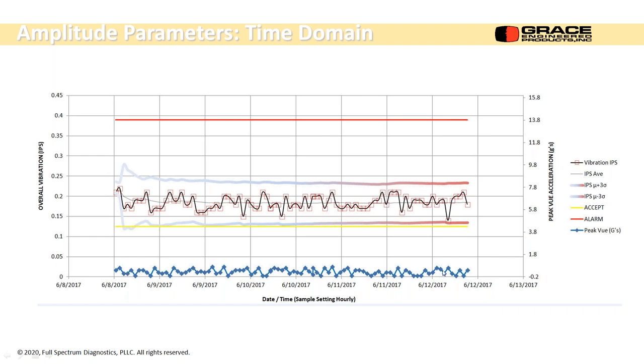All you're doing is filtering out the low frequency. You're using the same time signal that you've used before. It's just filtered a different way, and you're looking for the high frequency end faults instead of the low frequency. And all that can be trended as well. Very good rolling element bearing parameter for detecting those types of problems.